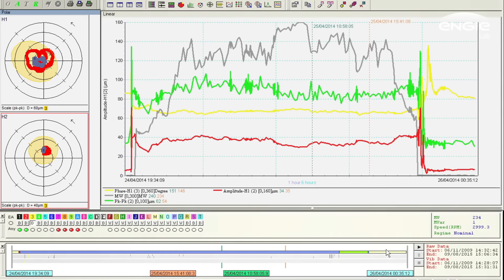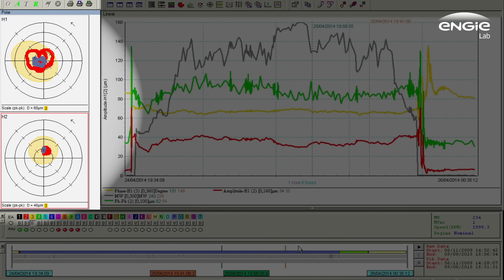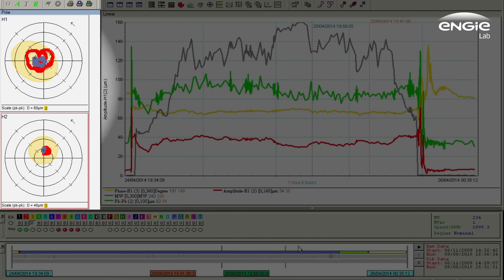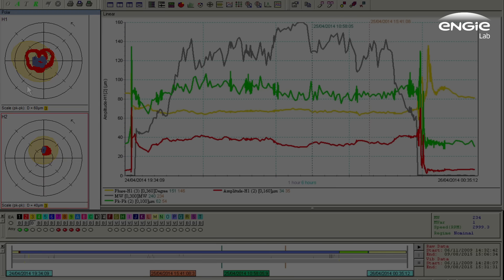Another strength of our software is the alarming strategy. Alarms are not only triggered on the global amplitude or the harmonic 1 amplitude or the harmonic 2 amplitude, but also they are triggered on an ellipse which is built around the vector as we can see here. So we will not only detect alarms when the amplitude is changing but also when the phase is changing.